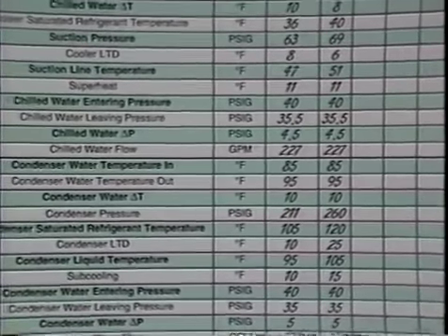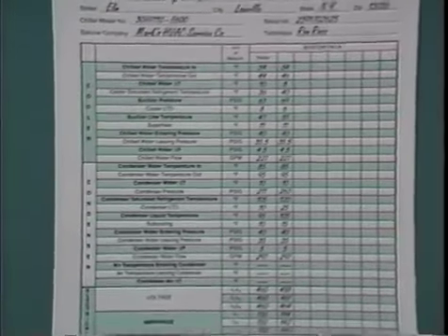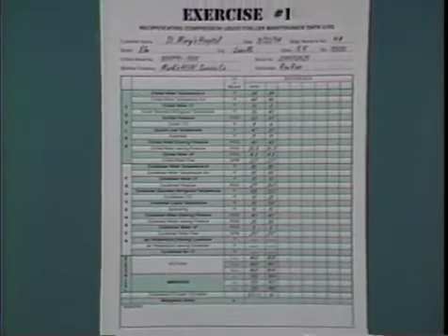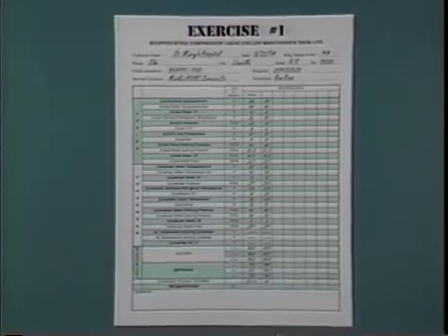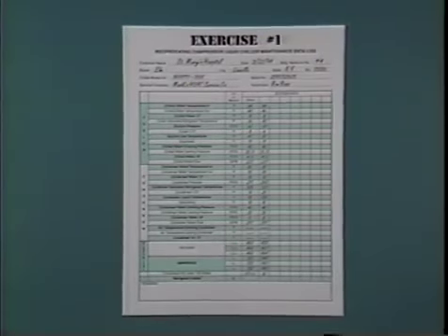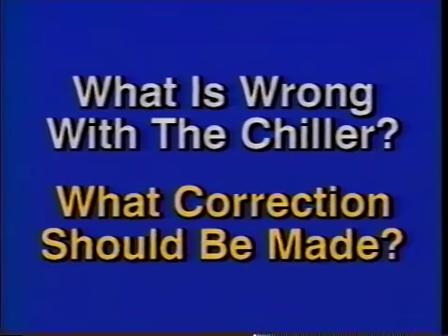In this exercise, we are troubleshooting a chiller with a water-cooled condenser, and as usual, the complaint is low capacity. Start by checking the delta T's and the LTDs. Then, look at the saturated suction and condensing temperatures, superheat, and subcooling. Determine what conditions are normal and what are abnormal. We want you to answer 2 questions. What is wrong with the chiller? And what correction should be made? Now stop the tape and go to your workbook and do exercise number 1. When you have completed the exercise 1, restart the tape for a review.